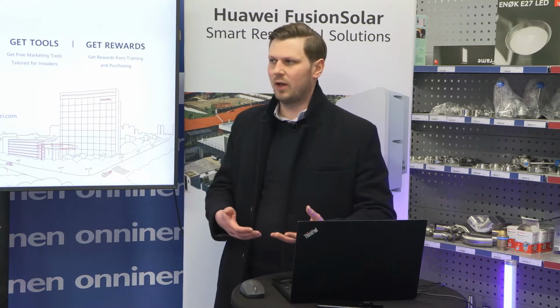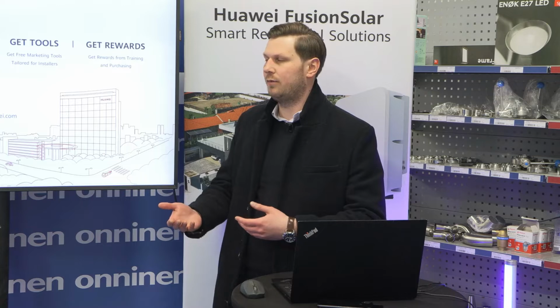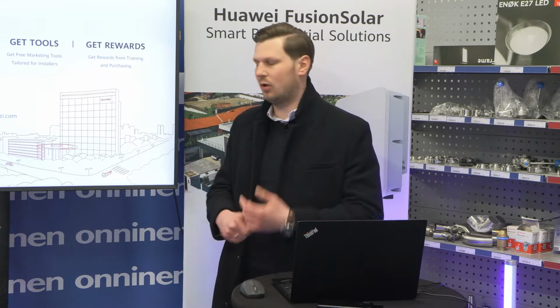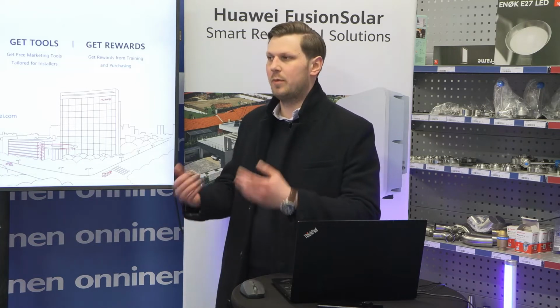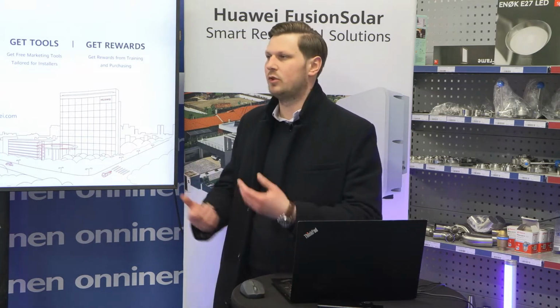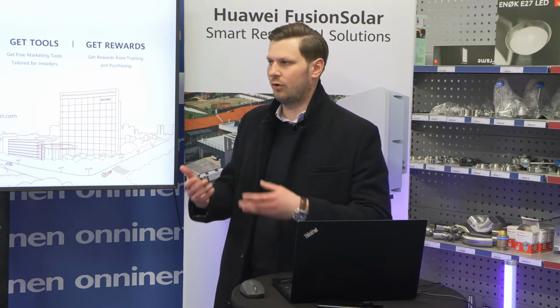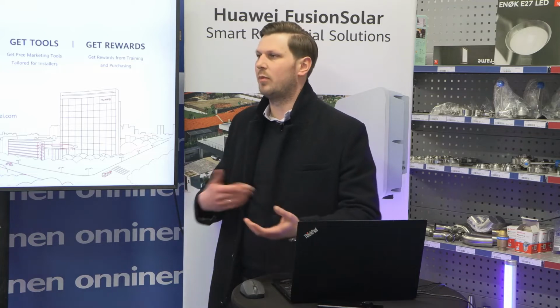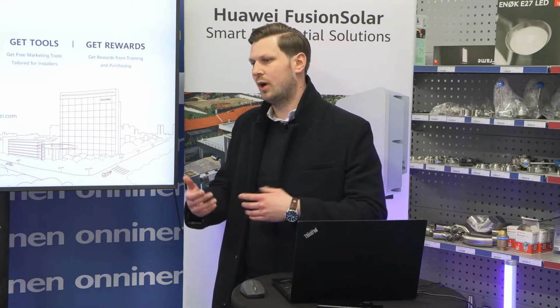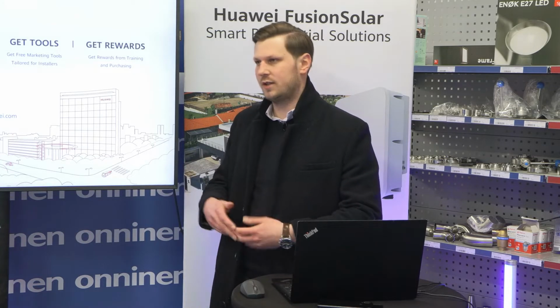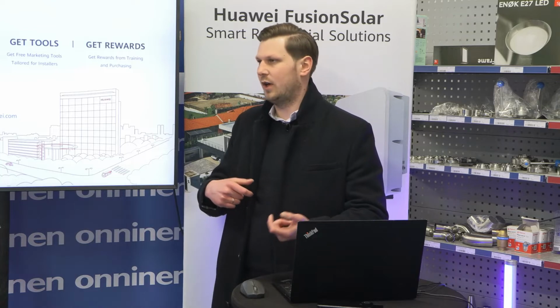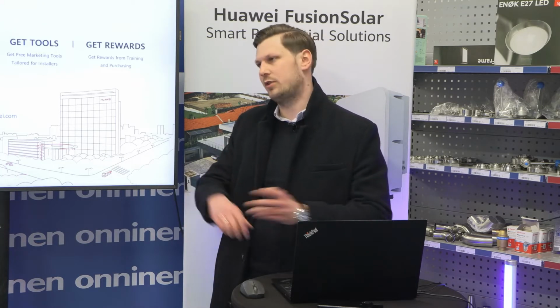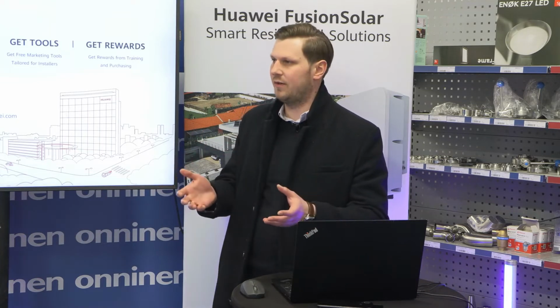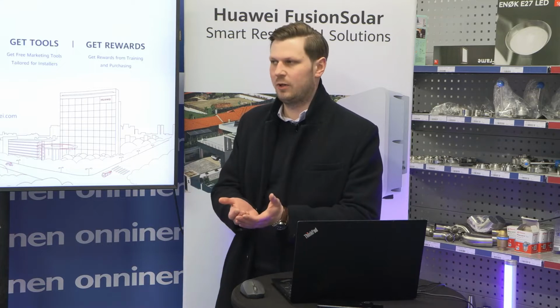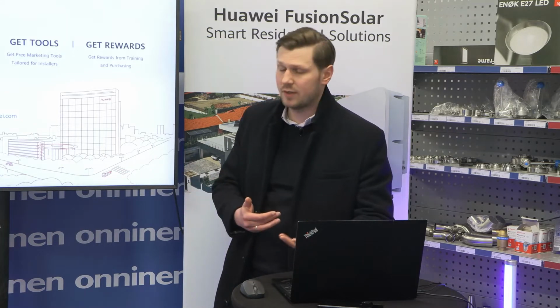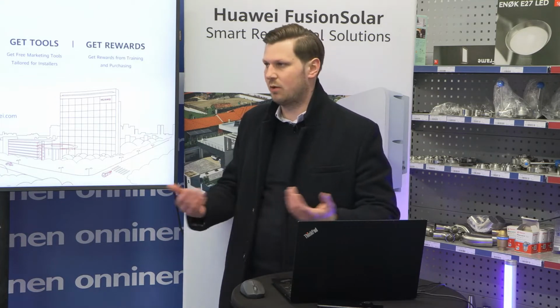But if it comes to warranty replacement, what you'll be asked for sure if you apply is to at least download the log files from the inverter, which might not be possible remotely if you don't have a connection with the Fusion Solar platform, so you have to do it on site. It's always best to make a short movie or some pictures describing and showing the problem. Sometimes what I'd suggest to do on site, just so you don't have to travel back and forth, is to do at least some basic measurements - we have the DC voltage, take a picture, we have the AC voltage, and make a short movie of how the inverter behaves. Then with the log files, it's the whole package of materials, and based on that, if we assume the inverter is faulty, it's just replaced under warranty. That's all you need.